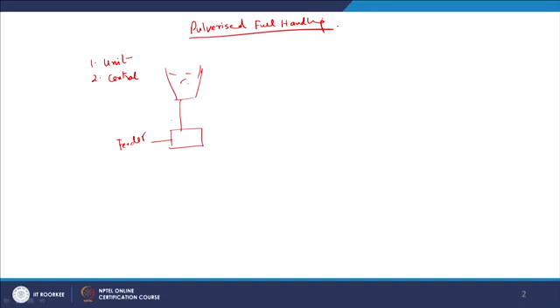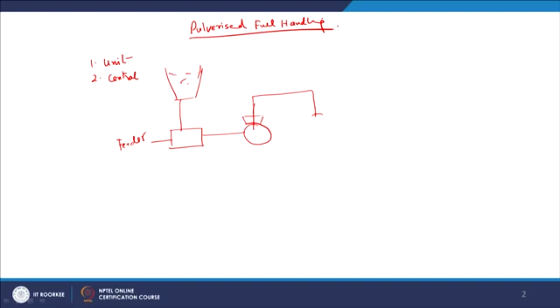where pulverization of the coal takes place, and a separator is also connected to the pulverizer. So, the mixture of fine particles of the coal, or the coal dust, and the air goes to an external fan. This is a fan, this is the pulverizer. Okay. From the fan it goes to the burner, where the burning of pulverized coal takes place. Now, there are two types of air supplied to the coal. One is the primary air, which is supplied from here. It is normally hot. So, primary air gets mixed with the fine dust particles of the coal, and this is how the movement of the fine dust particles of the coal takes place in the system.